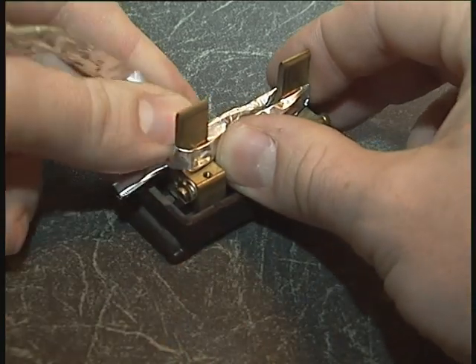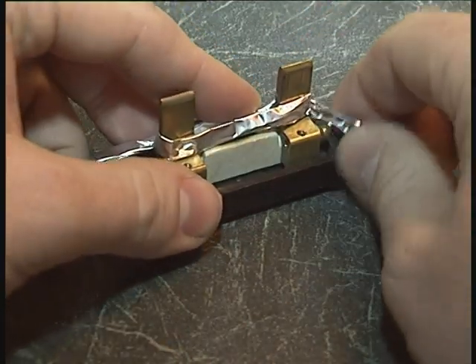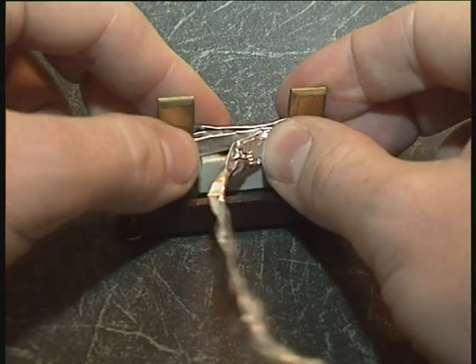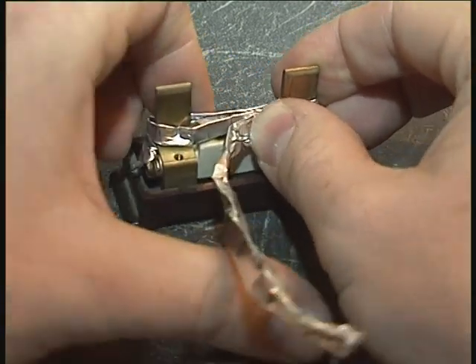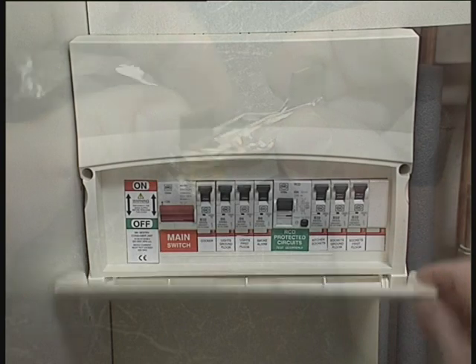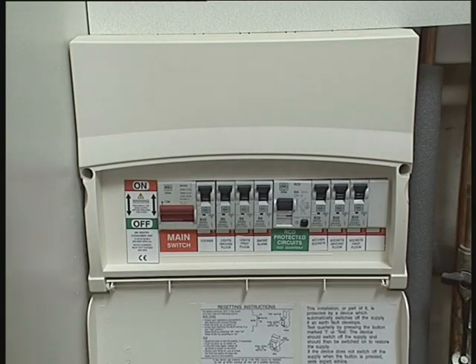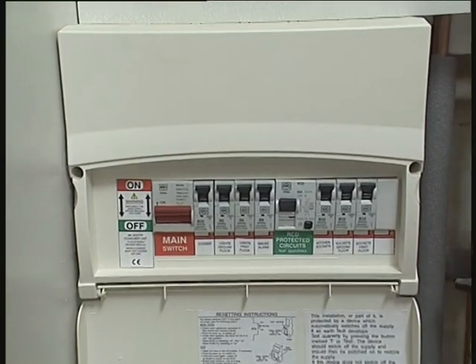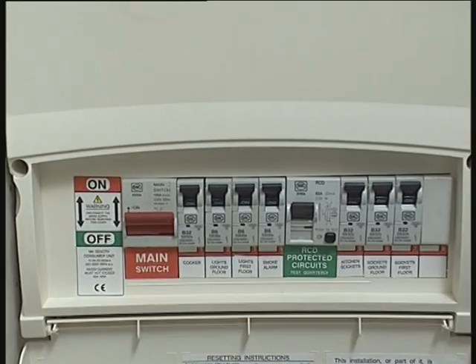Putting in a wire bigger than it should be, or in the worst case, wrapping foil around a fuse to get it working, are common causes of fires started by electricity. These days, instead of fuses, circuit breakers are used to protect the wires. These can be easily reset, so no need for replacing.